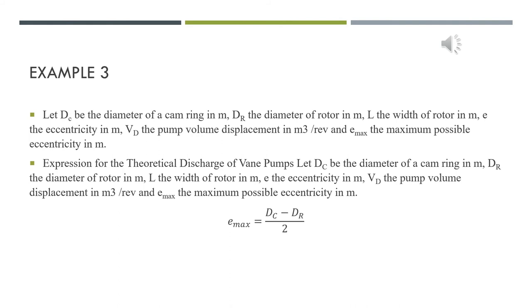Next, I am going to discuss how we find the eccentricity and the theoretical discharge by the pump. First of all, let Dc be the diameter of the cam ring, Dr equal the diameter of the rotor, L is the width of the rotor, E is the eccentricity, Vd is the pump volume displacement per revolution, and Emax is the maximum possible eccentricity. The maximum possible eccentricity equals the diameter of the cam ring minus the diameter of the rotor divided by 2.